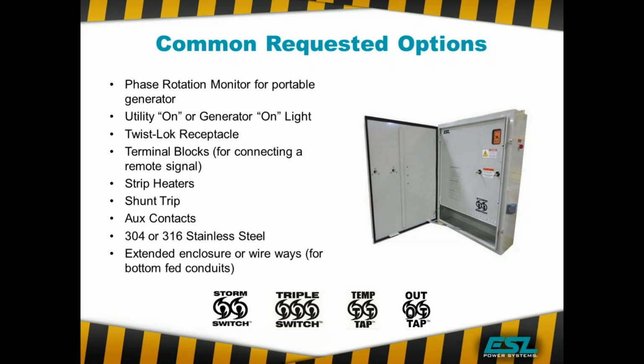There's the twist lock receptacle down there in the lower right-hand corner. That's so if you're going to pre-stage your portable generator, you can hook up battery chargers, heaters, and other types of accessories that they may want to plug in while it's being staged. And this would be something where you know a weather incident is going to come in, and you want to pre-stage the generator so that if you lose power, you can restore it very quickly.